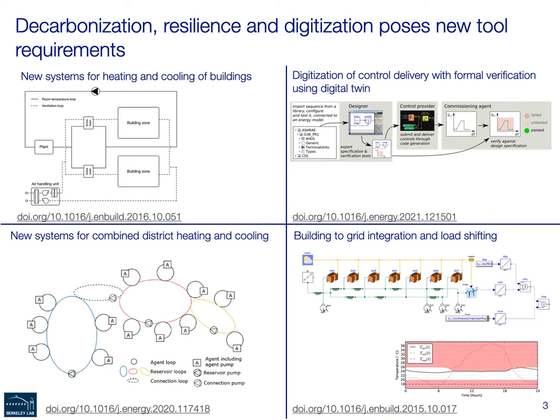On the other hand, digitization of control delivery processes allows us to share best practice control sequences, embedding them in a formal control delivery process with end-to-end verification, where the commissioning agent uses a digital twin to verify that the as-installed control sequence meets the design intent. This approach also allows us to share control sequences and best practices, not only within a company but across the whole building industry, and successively improve those sequences.